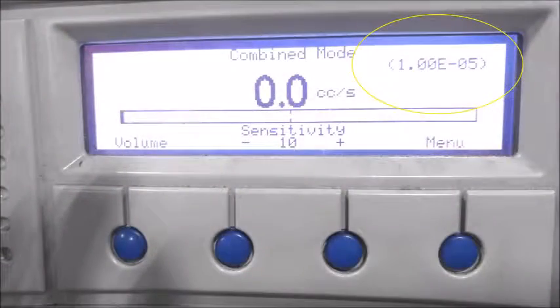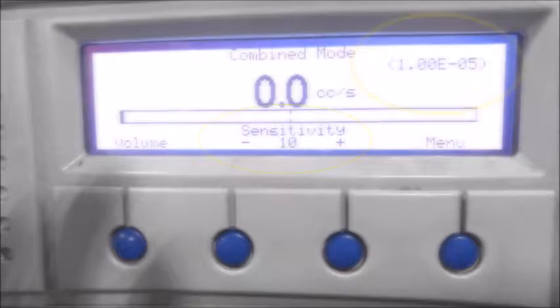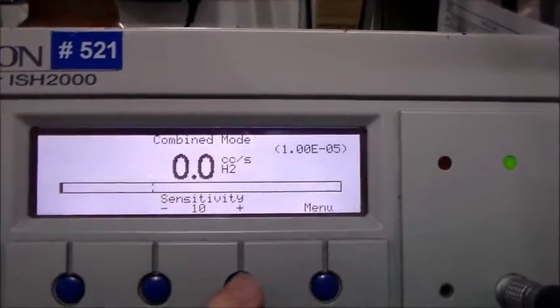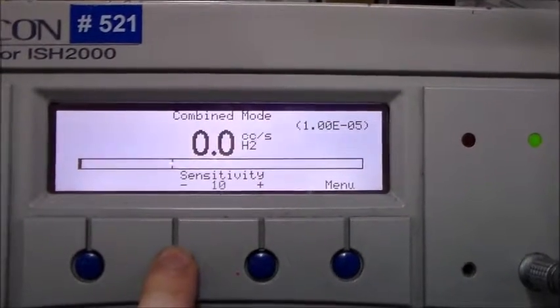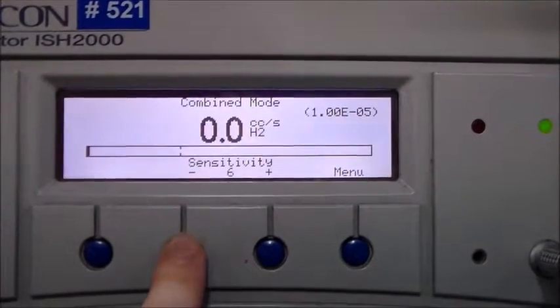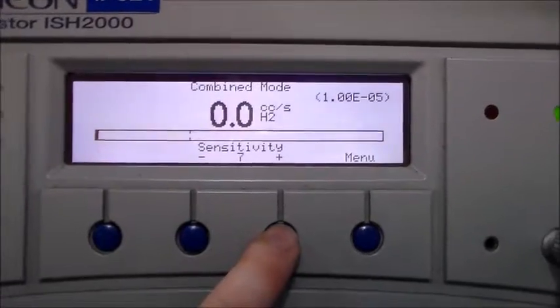Make sure the reject level is set to 1.00E minus 05 cubic centimeters per second. Contact your supervisor or lead to have manufacturing engineering change this if needed. Set the sensitivity level to 10. To adjust the sensitivity, press the sensitivity button, then set it using the plus or minus buttons.